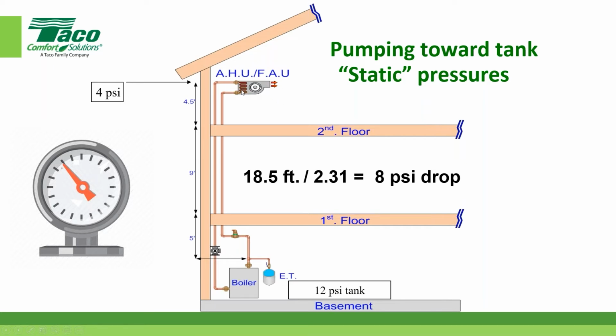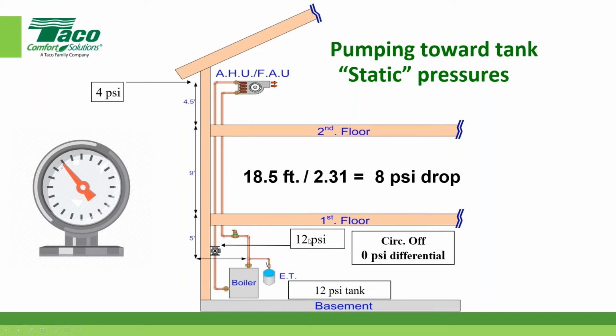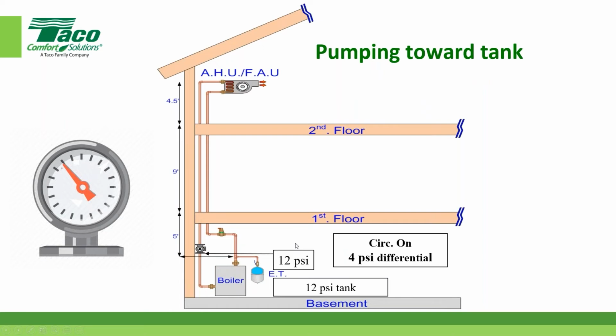There's nothing wrong with that. Okay, I've got a pressure differential. So when I turn things on, things might get a little crazy. Notice that when I turn it on, it starts out at 0 differential, but as soon as I turn it on, it pulls away that 4 psi. Now I take 4 off of that, I'm back to a big goose egg here. Or I could be negative, depending on how steep a pitch or flat pitch style circulator it is. I can actually go into the negative here. And if I have an auto air vent up here with a cap loosened up, like some people tell you to, you can actually pull air into the system. So I'm just showing you what happens.